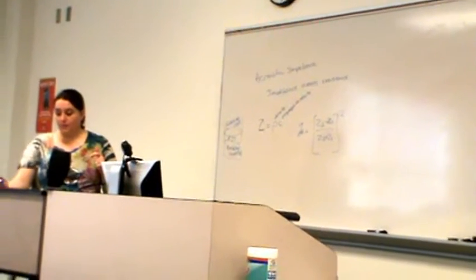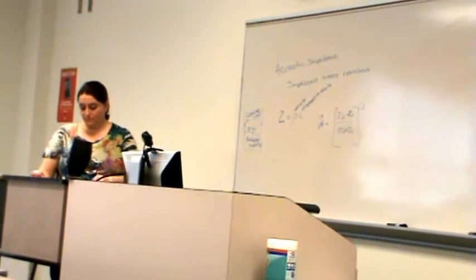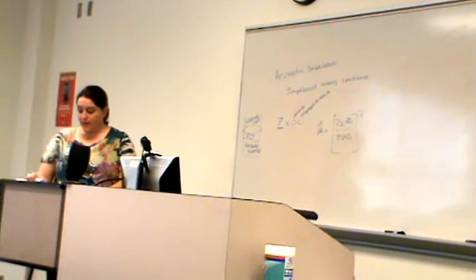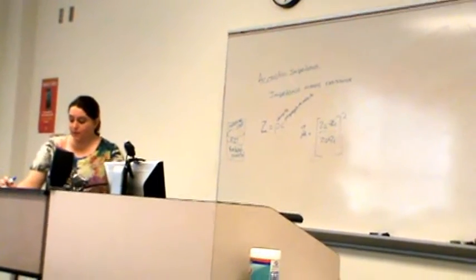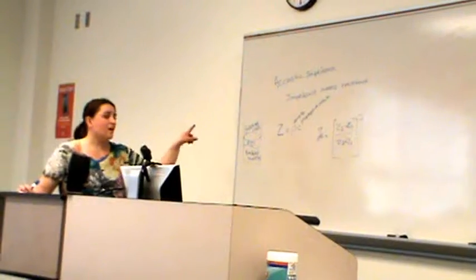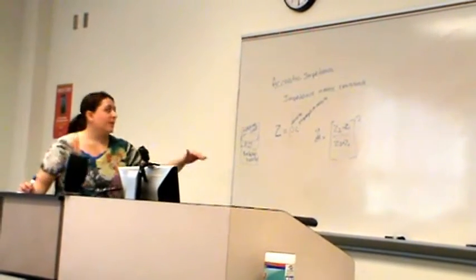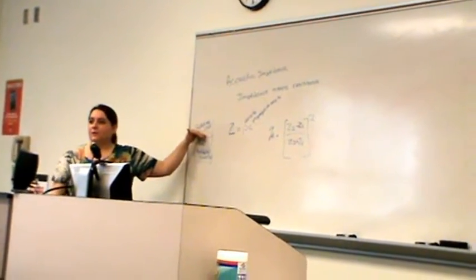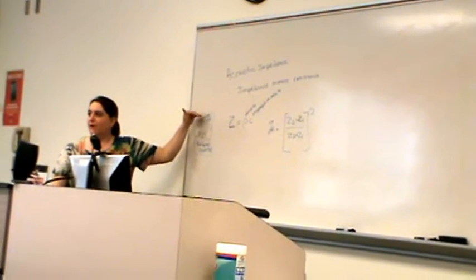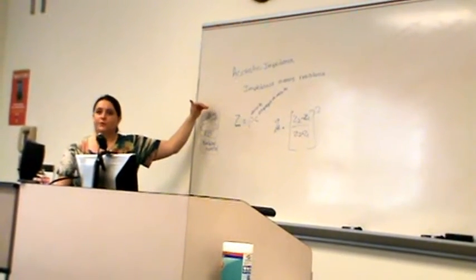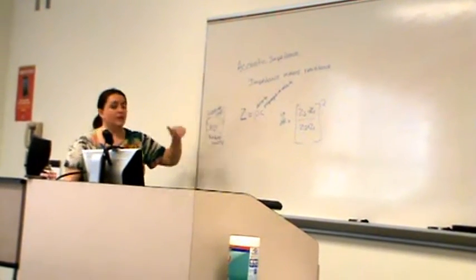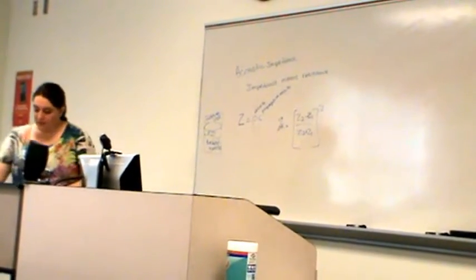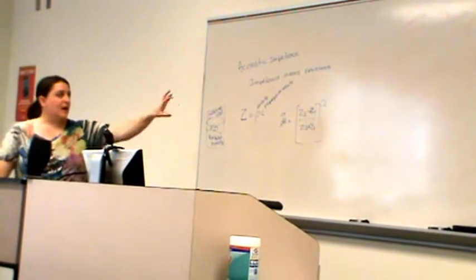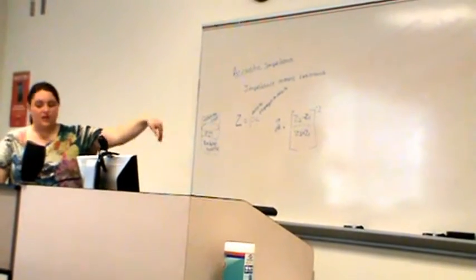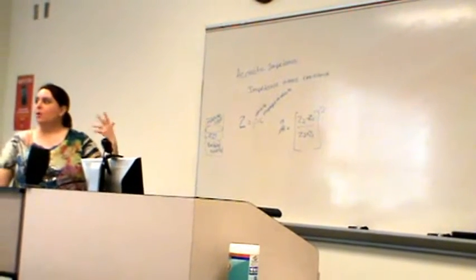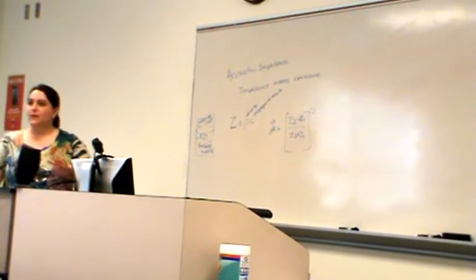Something matched up better. Let's see. Most transducers these days not only have one matching layer, but they have several. So the one that's touching the transducer face would have an acoustic impedance much closer to the crystal, and then as they move out away from the transducer face, they get closer and closer to the acoustic impedance of tissue. So it lessens that mismatch even more. But the idea of that whole mismatch thing is the larger the mismatch, the more reflection you get, the smaller the mismatch, the less reflections you get.